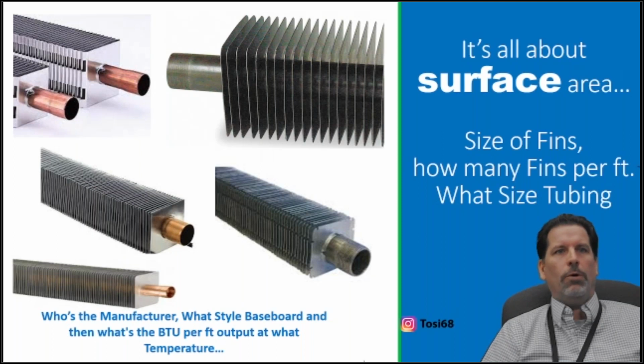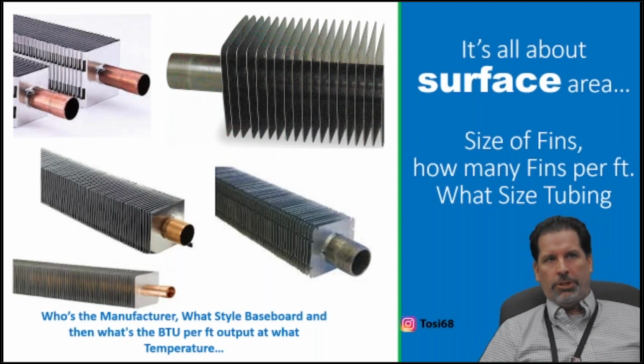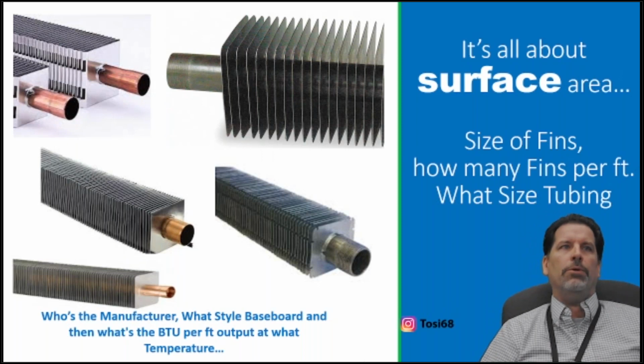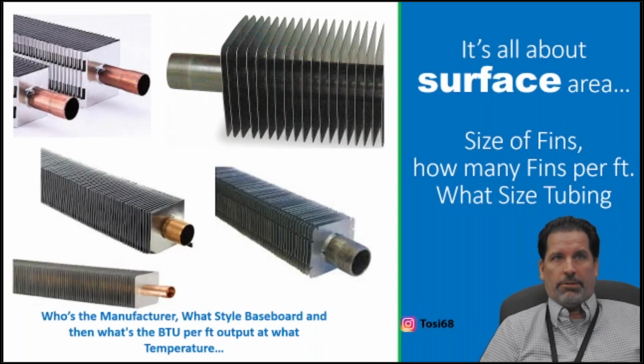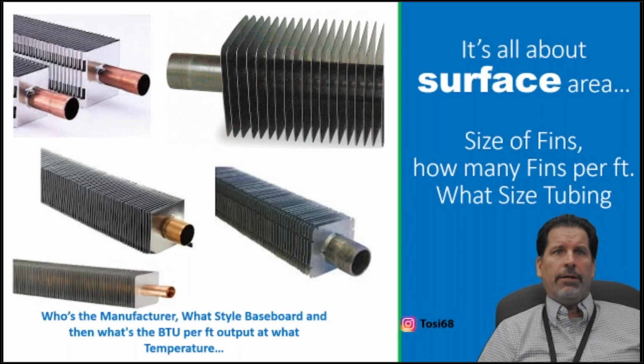If you're replacing an old boiler with a new one, get comfortable with understanding what the emitters are in every room. Take a measurement of the actual elements themselves, not so much the length of the room and the pipe and all that, but just the fins or whatever it is you have in there. We have charts to show you exactly how many BTUs for every foot of every kind of emitter out there. It's just given to us, whether we know it, see it, or don't understand it. That's what today is all about.